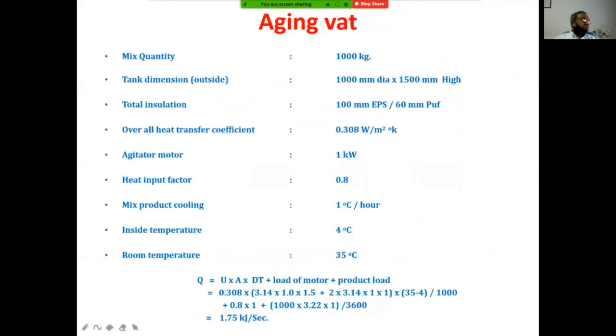How to calculate the load? It is, I can say, purely empirical judgment. There is some empirical judgment, and there is nothing like a theoretical formula that we can calculate by. But here we try to do it in a systematic way. What is the tank size, how the insulation is done, whether 100 mm EPS, expanded polystyrene insulation is done, or 60 mm PUF insulation, polyurethane insulation, is done. The overall heat transfer coefficient for this insulation is 0.308.